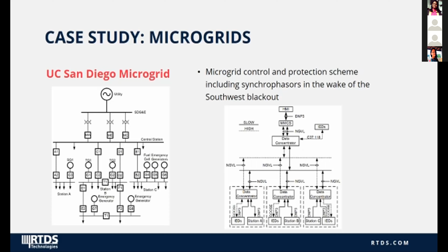The left side picture shows performance testing of this system with a digital real-time simulator prior to delivery, which was done by Schweitzer Engineering Laboratories. The right side figure shows the control system fulfilling its operational requirements, where a decoupling due to a frequency disturbance on the utility side results in shedding about 5 megawatts of load after the decouple.